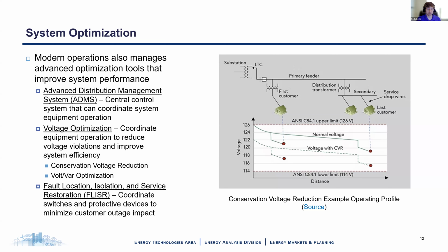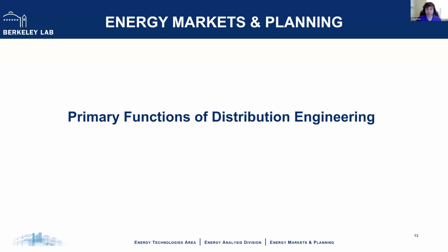The second one is FLISR, which stands for fault location, isolation, and service restoration. It goes through where is the problem, how do we separate the problem from the rest of the system, and which portions of the system can we still restore without getting them into the fault. And I'll show an example of this a little bit later on. But its goal is to coordinate the switches and protective devices to restore customers automatically when they can do so, and they're not impacted by faults.